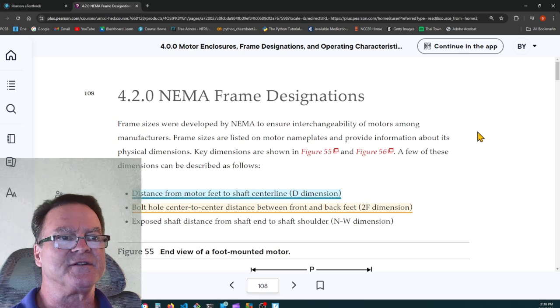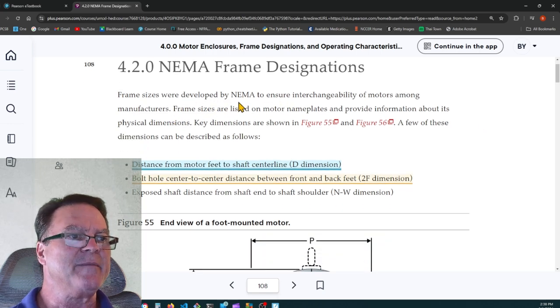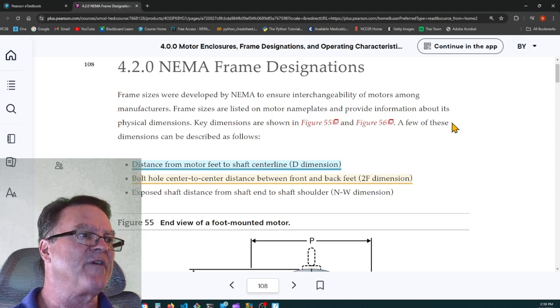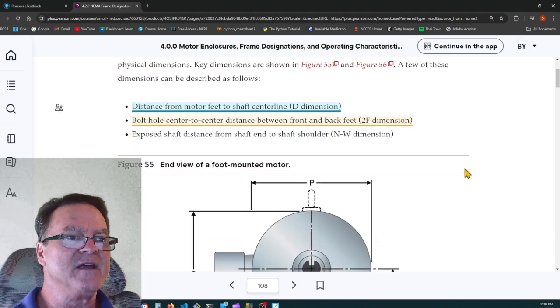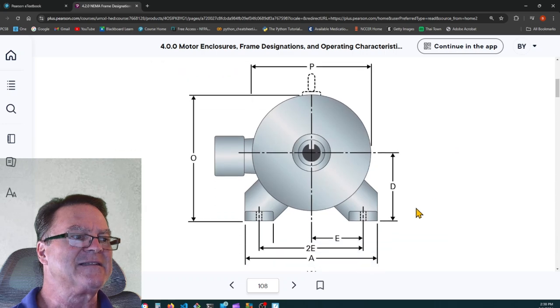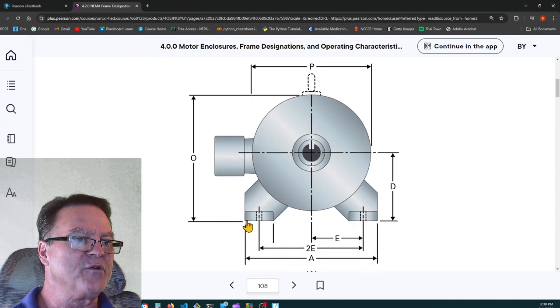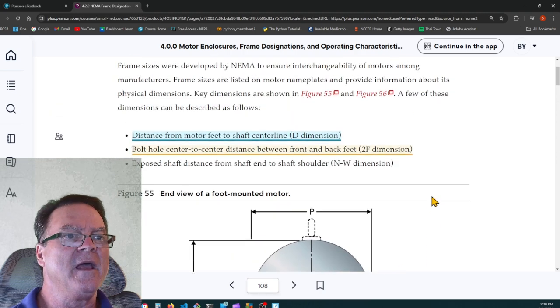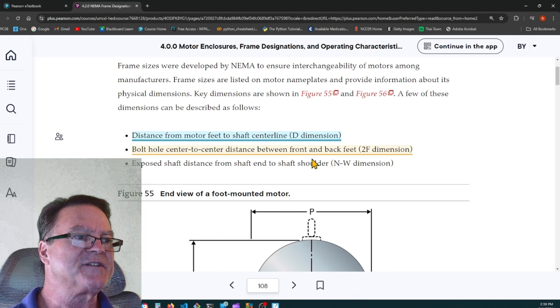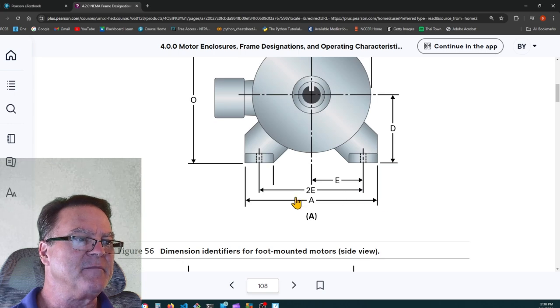NEMA frame designations. Frame sizes were developed by NEMA, again, that's the National Electrical Manufacturers Association, to ensure interchangeability of motors among manufacturers. Frame sizes are listed on motor nameplates to provide information about the physical dimensions. So here's a highlight. It says, the distance from the motor feet to the shaft center line is the D dimension. So here from the motor feet to the center line of the shaft, that's the D dimension. And the hole center to center distance between front and back feet is the 2F dimension.